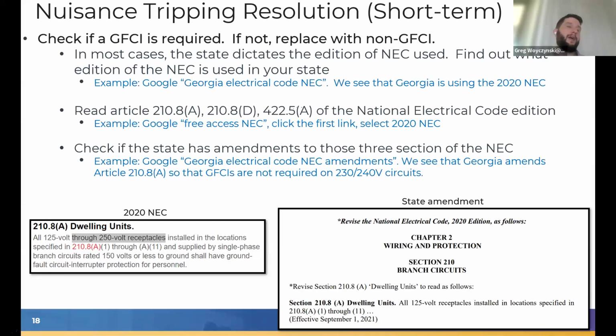The state of Georgia has taken action to make sure that nuisance tripping doesn't occur. So just to better explain that, here's a screenshot from the 2020 NEC, which says that all 125 volt through 250 volt receptacles are required to be connected to a GFCI. Then we have the state amendment that takes out this through 250 volt part. It just says all 125 volt receptacles are required to be connected to a GFCI.